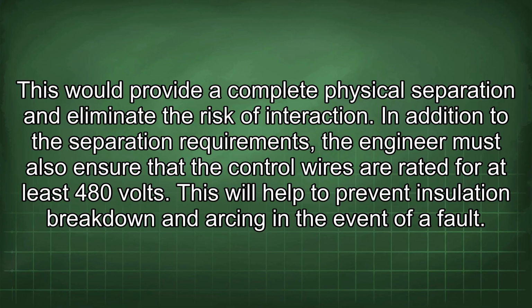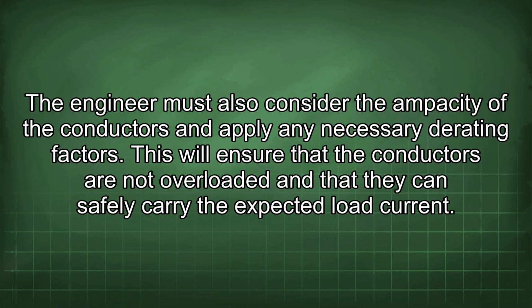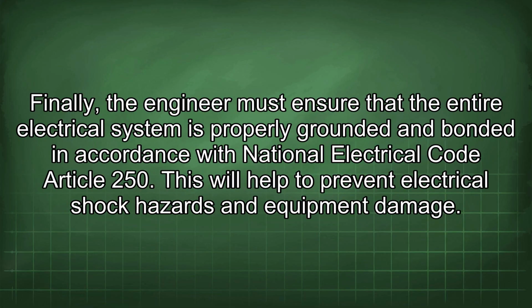In addition to the separation requirements, the engineer must also ensure that the control wires are rated for at least 480 volts. This will help to prevent insulation breakdown and arcing in the event of a fault. The engineer must also consider the ampacity of the conductors and apply any necessary derating factors. This will ensure that the conductors are not overloaded and that they can safely carry the expected load current. Finally, the engineer must ensure that the entire electrical system is properly grounded and bonded in accordance with National Electrical Code Article 250. This will help to prevent electrical shock hazards and equipment damage.